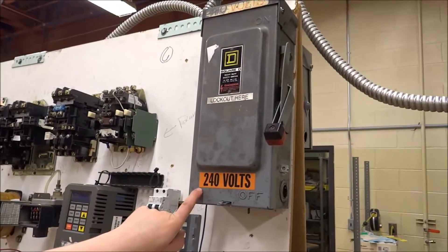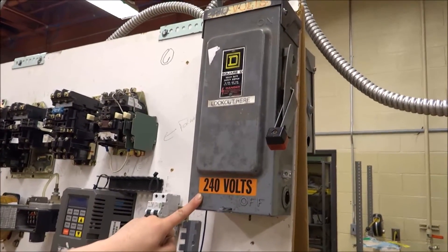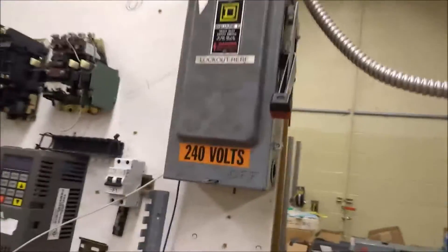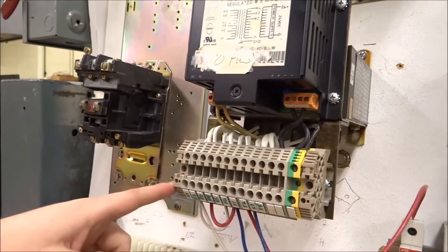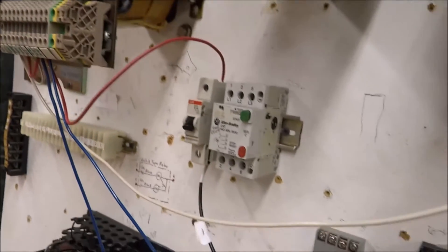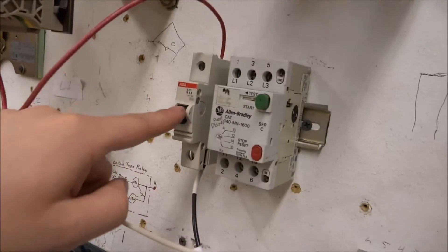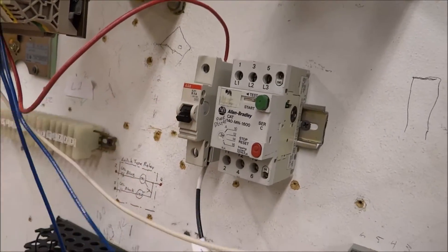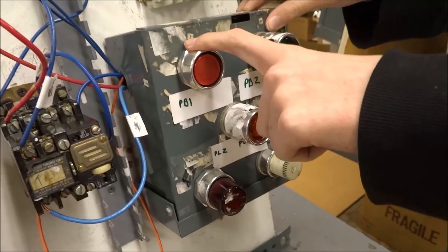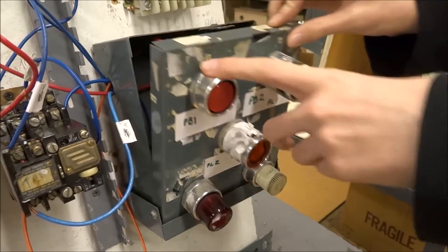In our panel box, we have 240 volts coming into our transformer. And from the 240 volts, it's getting reduced to 120 volts coming out of the transformer into the 15 amp breaker we have set. From there, into the stop button. The stop button goes to the start button, which is the green one.